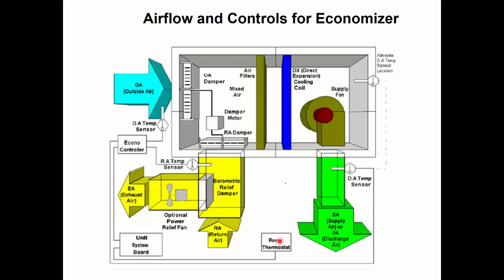He closes the relay that says, give me cooling. That signal goes up to the circuit board up in the rooftop unit. But what ends up happening is it doesn't go there on an economizer job. Instead, that signal gets intercepted and run over to the economizer damper controller. And then that guy looks at the outdoor conditions or the differential conditions, depending on what system you have, and decides, is it nice outside for free cooling? If it's not, and it's too warm outside, it says, okay, I'm going to go ahead and pass that signal you gave me over to the compressor and run it like you want.